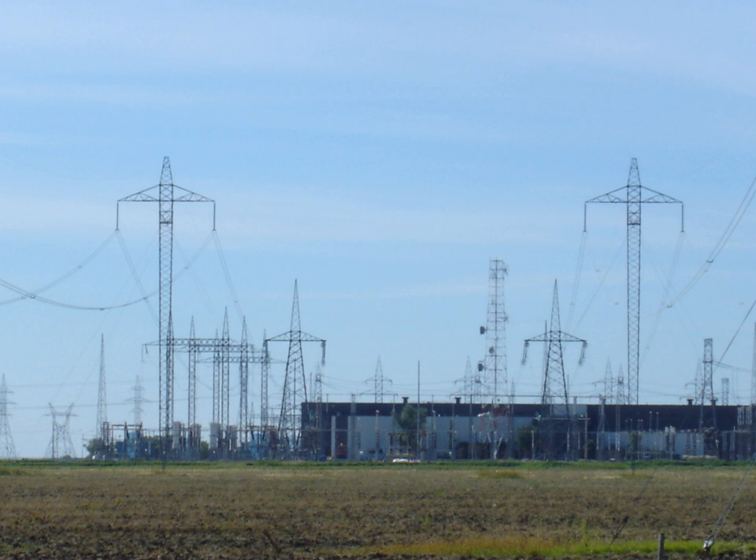An alternative is to use two high-voltage conductors operating at about half of the DC voltage, with only a single converter at each end. In this arrangement, known as the symmetrical monopole, the converters are earthed only via a high impedance and there is no earth current. The symmetrical monopole arrangement is uncommon with line-commutated converters, but is very common with voltage-sourced converters when cables are used.